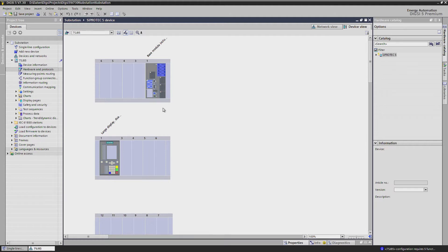Which protocols are running on the communications modules is not fixed during the ordering process, but is flexibly defined in DIGSI 5. This gives you the freedom to change the protocol running on a certain communications module whenever you require it. You can keep the module and just change the protocol selection in DIGSI 5, provided the new protocol is of the same type. A serial protocol can be replaced by another serial protocol and an Ethernet protocol by another Ethernet protocol.